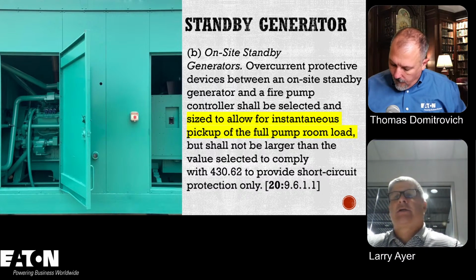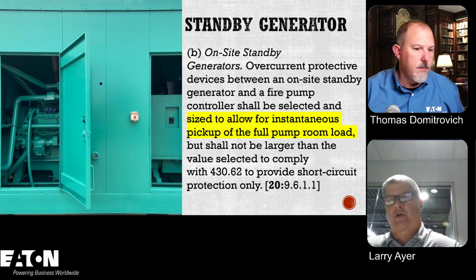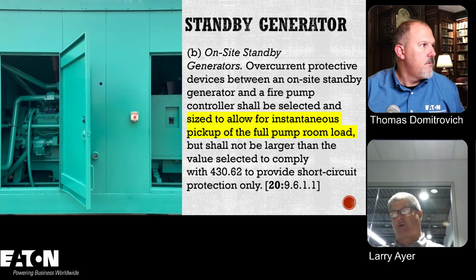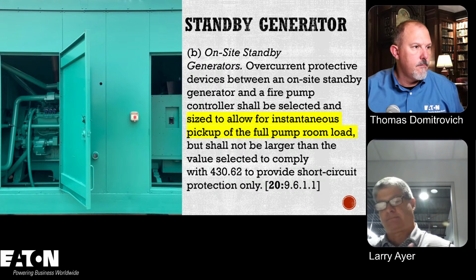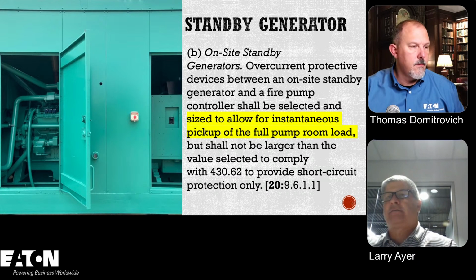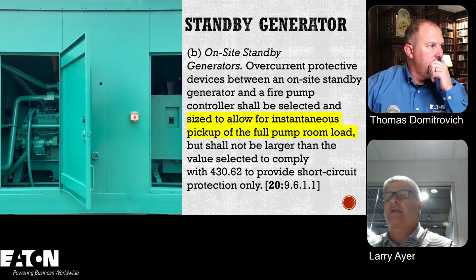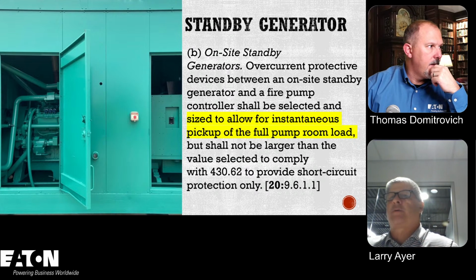So again, A, you need to worry about locked rotor for your individual sources. B, if it's a standby generator, we don't need to worry about that. So we basically can put our overcurrent device in for the generator and just size it, correlating it 125%, the wire and things like that, and go ahead and do it as you normally would do a motor. Perfect.